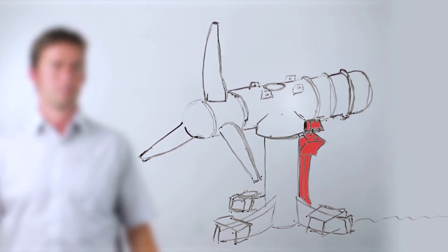One of these is the connection management system. The connection management system is what connects the turbine to the subsea cable that will export the power to the grid. Traditionally, the connection management system would use what we call dry-mate connectors, which need to be engaged when they're not submerged.